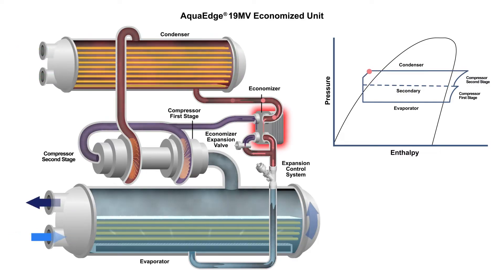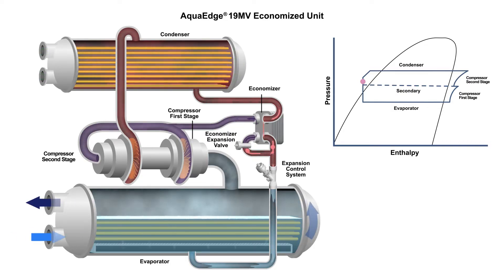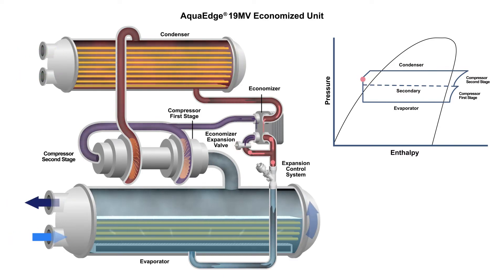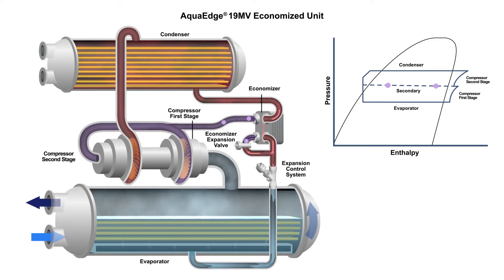In the economizer section, the refrigerant directly enters one side of a brazed plate heat exchanger. After passing through one side of the heat exchanger, the high-pressure liquid refrigerant is divided, creating a secondary flow which is directed through an expansion valve. The liquid refrigerant's secondary flow is reduced to an intermediate pressure and then fed into the other side of the heat exchanger. The secondary flow boils into a vapor, absorbing energy from the primary flow through the plates in the heat exchanger. The high-pressure primary flow refrigerant is cooled, which increases its capacity to absorb heat in the evaporator.